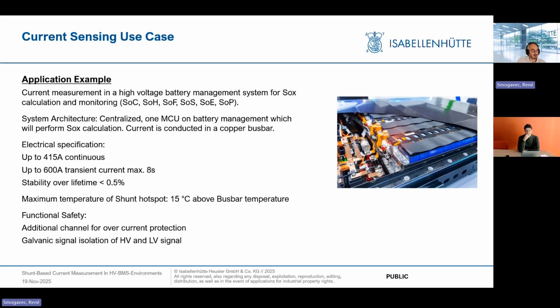The specifications, which can be way bigger than this, but are often really sufficient for a good first offering: 415 amps continuous, 600 amps transient current, max 8 seconds. So more or less a pulse load, max 8 seconds, treating it as if it's a continuous 600 amp RMS current. So nothing to calculate or simulate here. Stability over lifetime is also quite normal with 0.5. Temperature headroom is 15 degrees Celsius, and functional safety is also very basic here, to give you an idea of what is usually designed in.